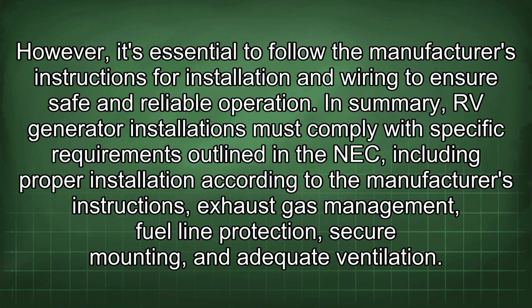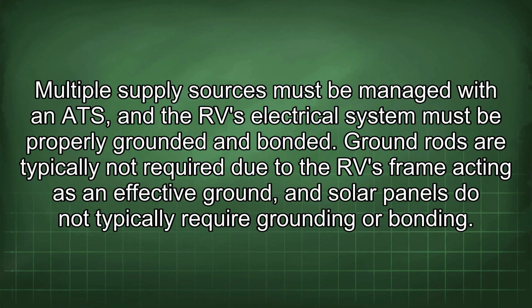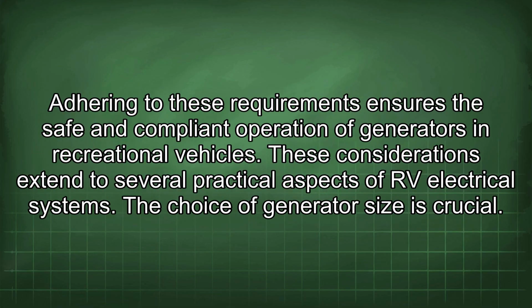In summary, RV generator installations must comply with specific requirements outlined in the NEC, including proper installation according to the manufacturer's instructions, exhaust gas management, fuel line protection, secure mounting, and adequate ventilation. Multiple supply sources must be managed with an ATS, and the RV electrical system must be properly grounded and bonded. Ground rods are typically not required due to the RV frame acting as an effective ground, and solar panels do not typically require grounding or bonding. Adhering to these requirements ensures the safe and compliant operation of generators in recreational vehicles.